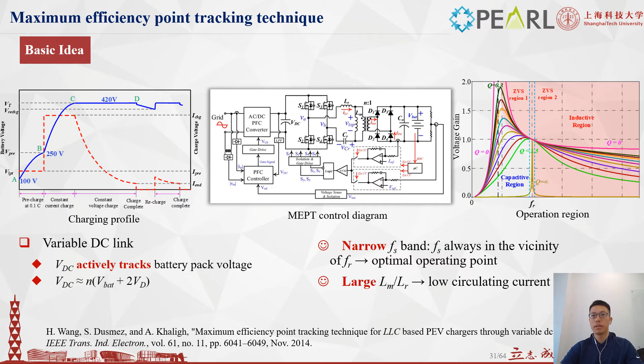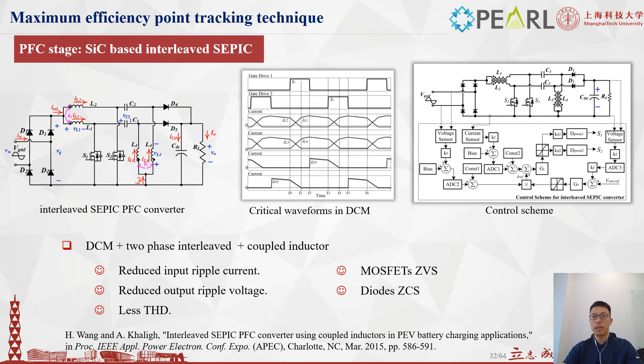However, the variable DC link voltage also brings new challenges to the front stage AC-to-DC power factor correction stage. To realize an ultra-wide DC bus voltage range, the conventional boost topology is no longer suitable here. To resolve this issue, we propose using a SEPIC power factor correction solution, combining DCM with two-phase interleaving plus coupled inductor to optimize performance. Utilizing this combination, we can reduce the input current ripple and the output voltage ripple and the total harmonic distortion. Moreover, we can realize zero voltage switching of the MOSFETs and zero current switching of the diode.